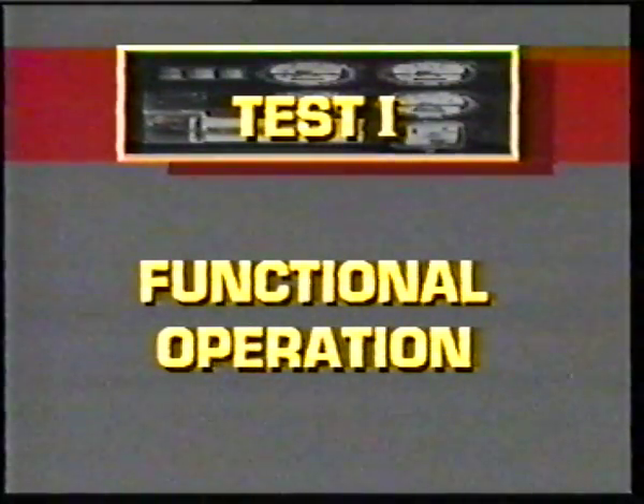This test for functional operation is virtually a final resume of preceding tests, which would have normally established that the installation or the portion under test can be safely connected to the supply. Following either permanent or temporary connection to a supply, a check should be conducted to verify, as far as practicable, that the installation operates as required and expected.